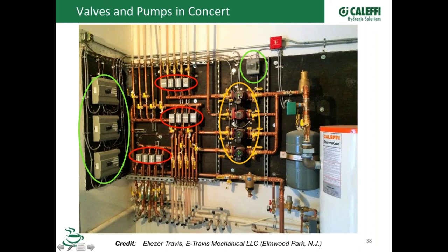You can see he's got delta P pumps on these ones that have multiple zone valves. So the zone valves open and close. These three pumps here are going to ramp up and down. He's got air separation where it should be, low water cutoff. I mean, this is probably the textbook example of how a system could or should be piped as far as access to everything.